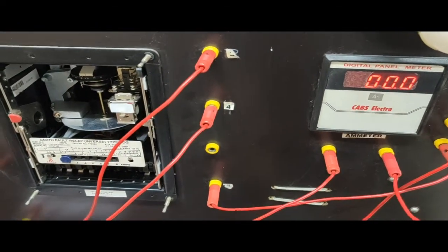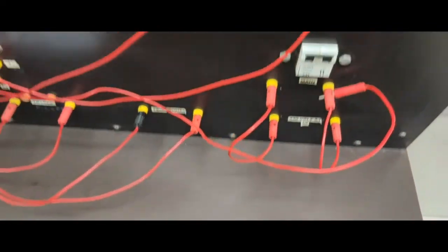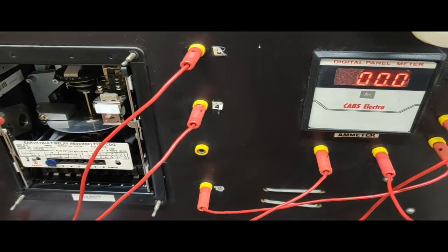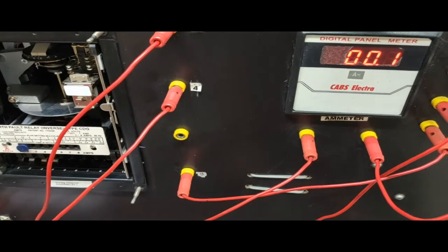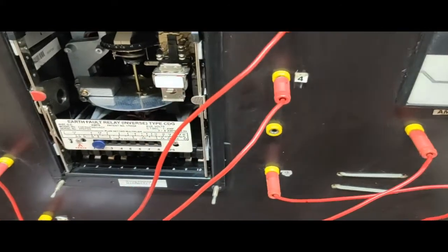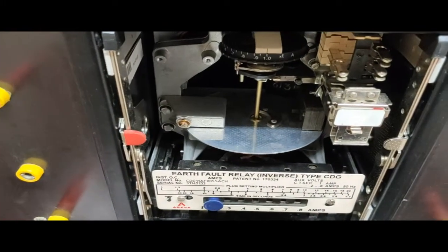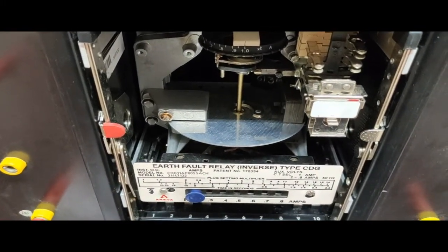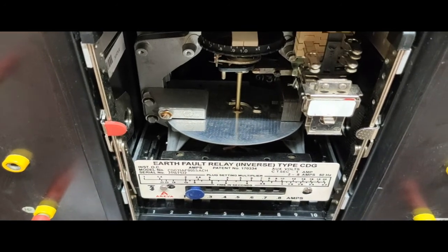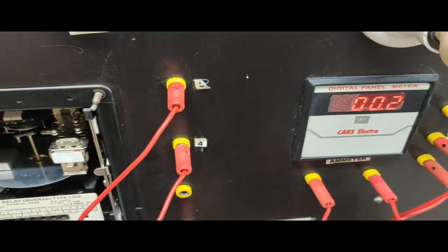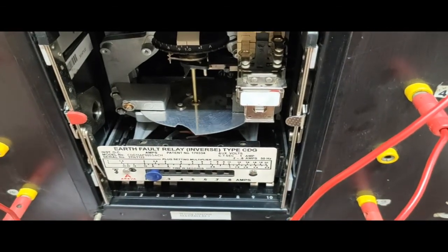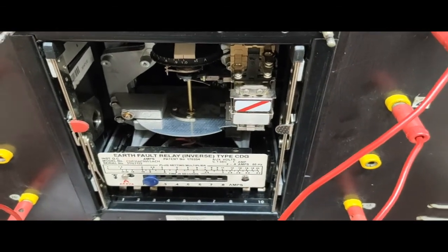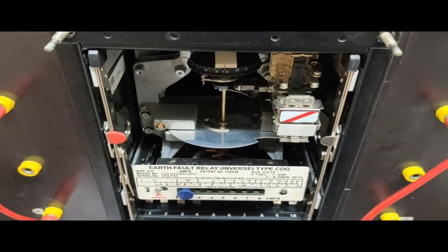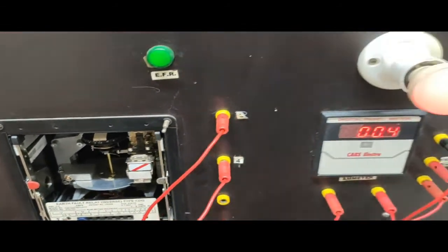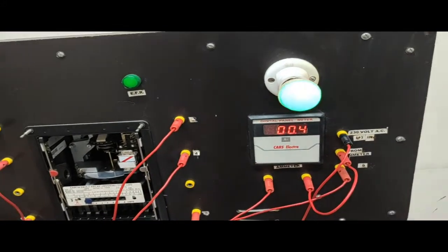Then we need to give some voltage so that the required current will flow through that relay. So I am just moving the variac, and let's see the operation of the relay. So here you see that till now there is no current flowing through the relay. 0.1, you see as the current is 0.2, the disk has started moving very slowly. Okay, so that's the threshold value, the disk has started moving, and if I increase the value of current, the disk will move faster. And you see the relay has actually short circuited the tripping coil, so the plug goes down, and this indicates that the relay has generated the trip signal already.